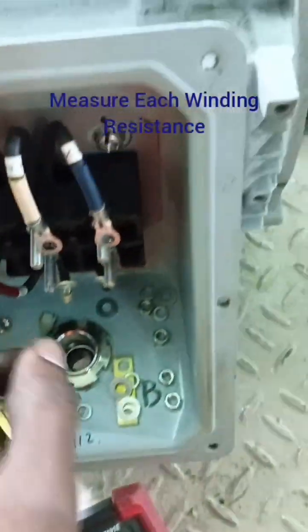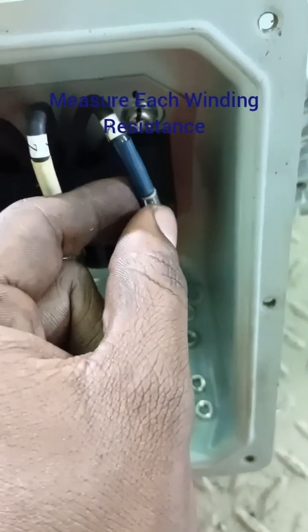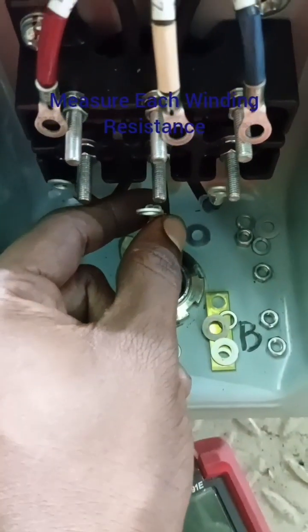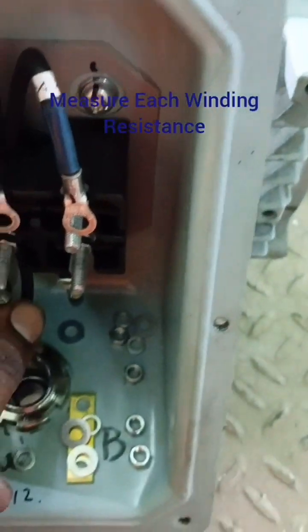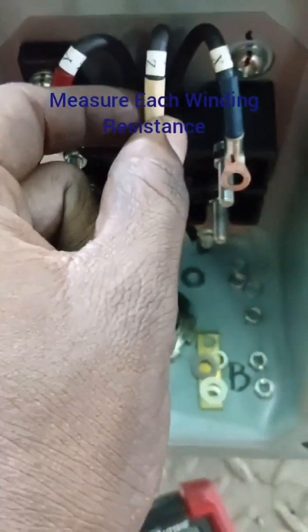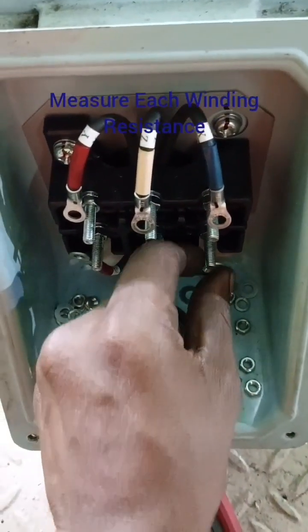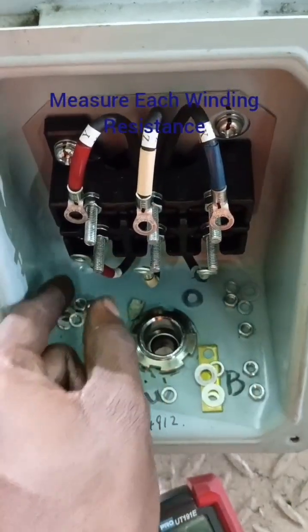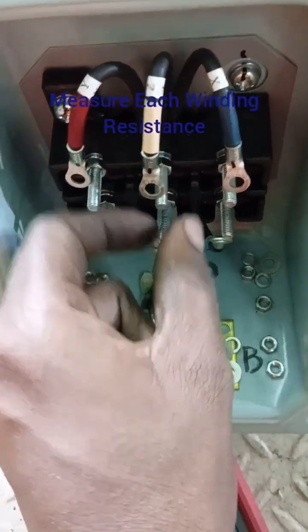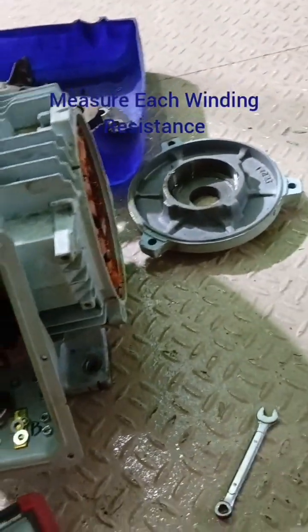Next, I disconnected everything. Now we are going to measure resistance of each winding, like the U1 and U2 terminal, V1 and V2 terminal, W1 and W2 terminal. So we can come to know what the resistance of each winding is. Let's check.